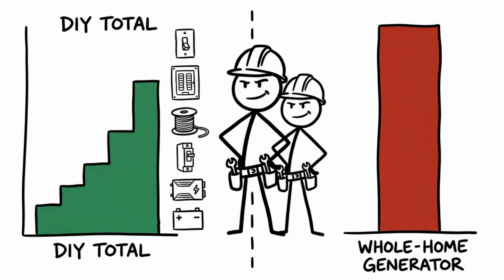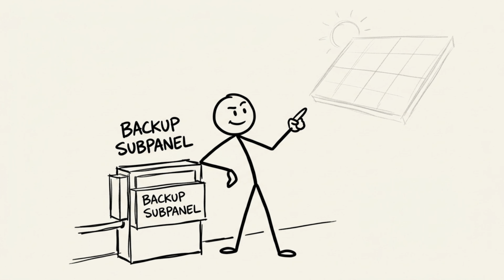Add up the transfer switch, the subpanel, the wire, the breakers, the inverter, and the battery bank, and you land well under what a fully installed whole home standby generator system costs. You're buying a specific, correctly sized set of circuits that keep running when everything else in the neighborhood goes dark, and the same critical load subpanel you just built is the exact foundation the next system, a solar charging array, will plug straight into.